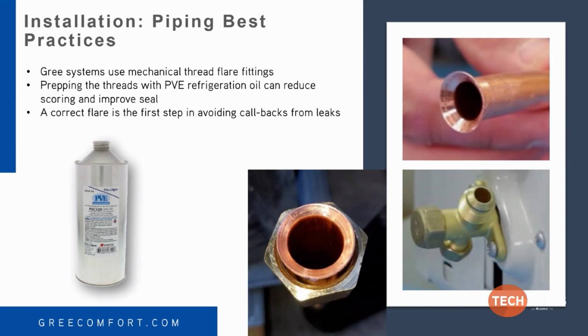Gree systems use mechanical thread flare fittings. Prepping the threads with refrigeration oil can reduce scoring and improve the seal. You'll notice on the slide it says PVE refrigeration oil, because that's what's used in Gree systems. It's not POE. PVE oil is less hygroscopic and longer lasting.